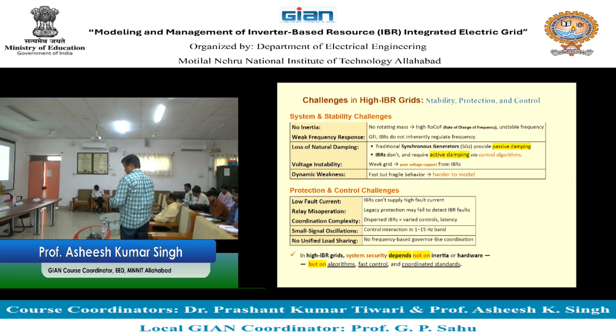Clear? GFL modes fail to maintain stability, leading to protection issues, voltage collapse, or poor frequency regulation. GFM IBRs can directly address lack of inertia by emulating inertial response through control. Against grid voltage collapse, they can be controlled to act as a voltage source. So through control they can remain stable throughout the fault and normal conditions, and they have the capacity of providing black start flexibility, means they can energize dead grids independently. Clear?